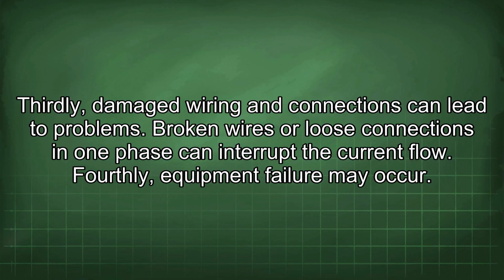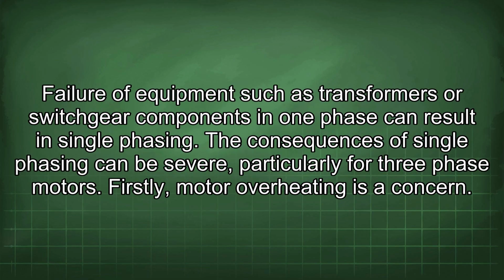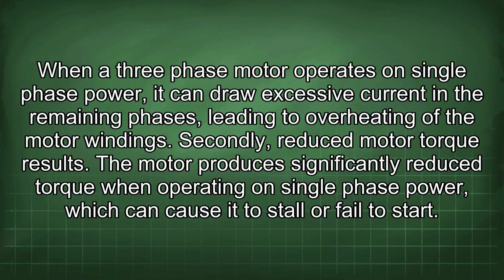Fourthly, equipment failure may occur. Failure of equipment such as transformers or switchgear components in one phase can result in single phasing. The consequences of single phasing can be severe, particularly for three-phase motors. Firstly, motor overheating is a concern. When a three-phase motor operates on single-phase power, it can draw excessive current in the remaining phases, leading to overheating of the motor windings.